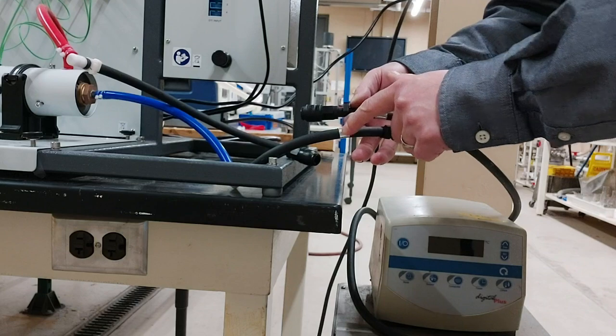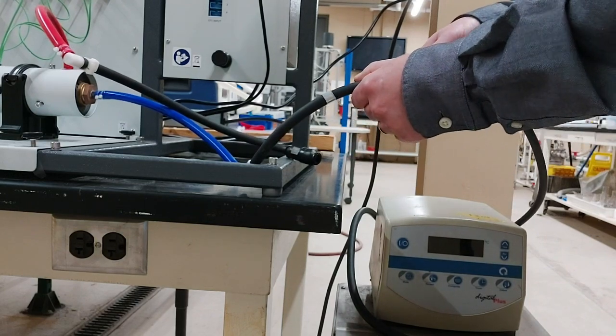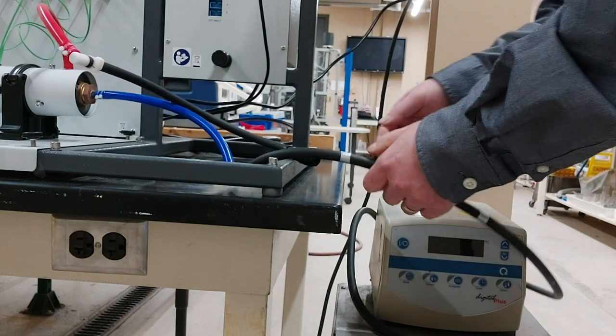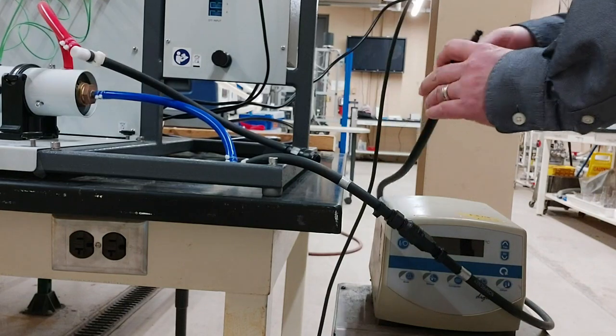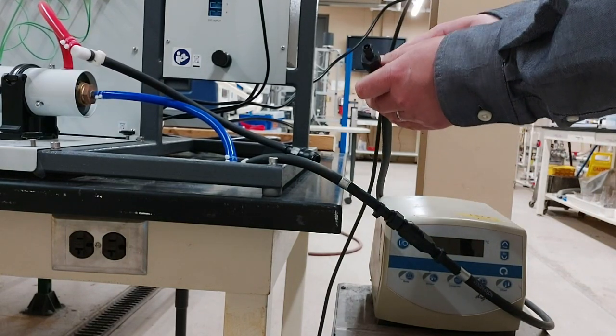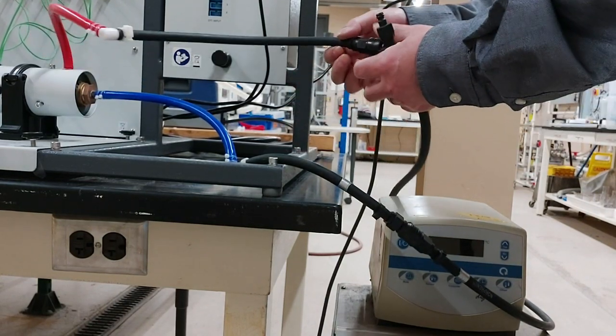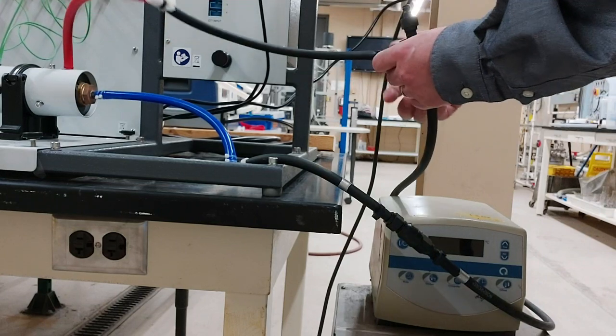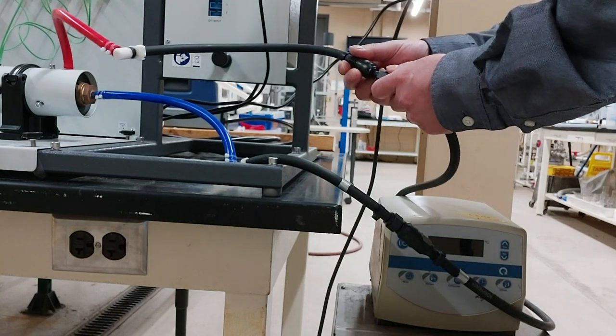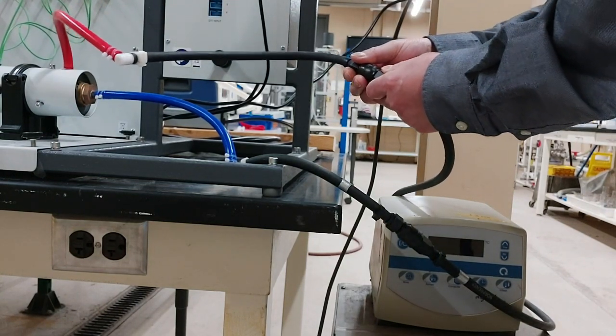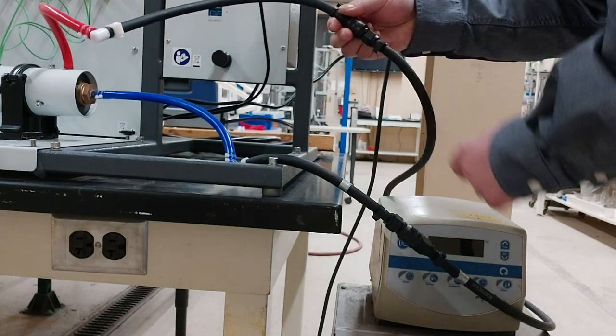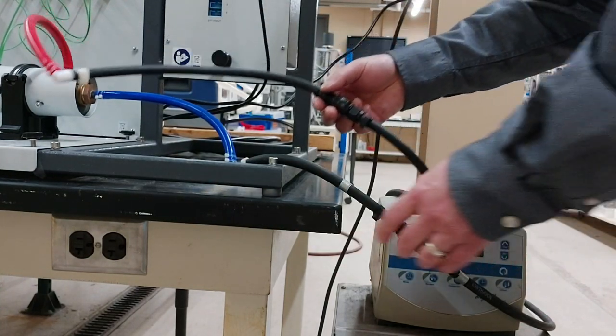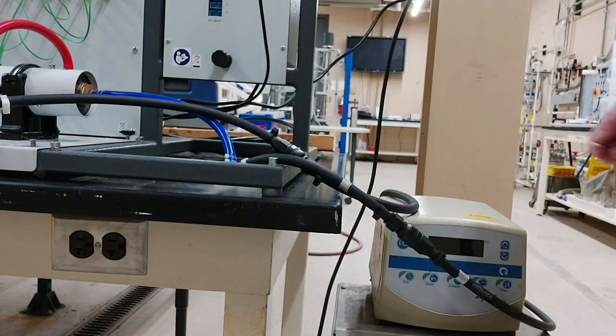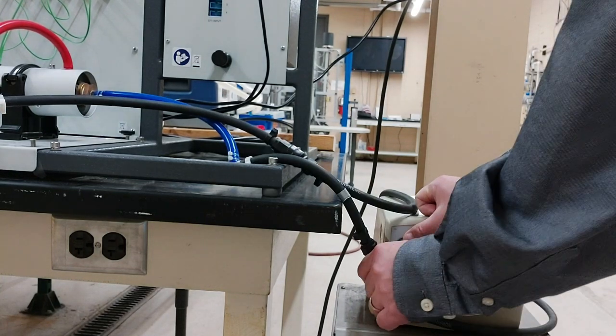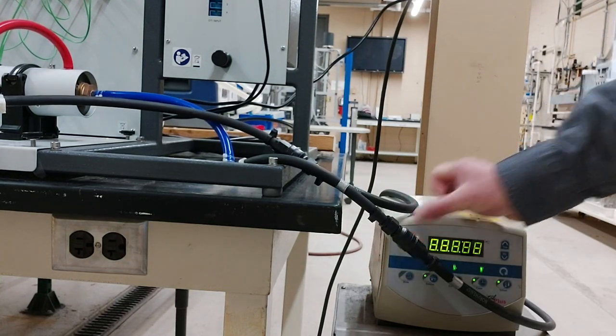You can see the silver duct tapes to match. Likewise, connect the recirculating chiller's return water tube to the instrument's outgoing water tube that is connected to the red tube. Now, all the tubes are connected in a big circle. It's time to start the chiller by pushing this power button.